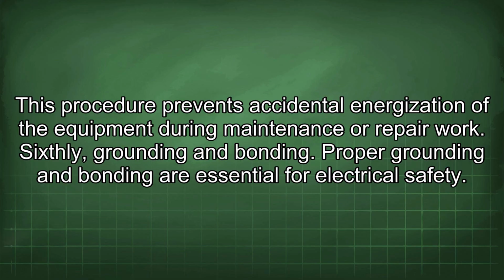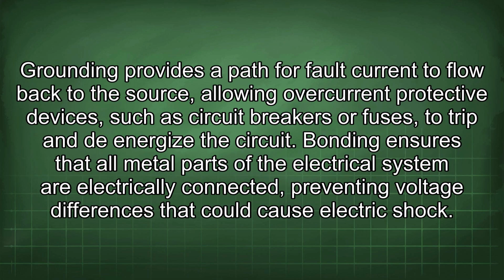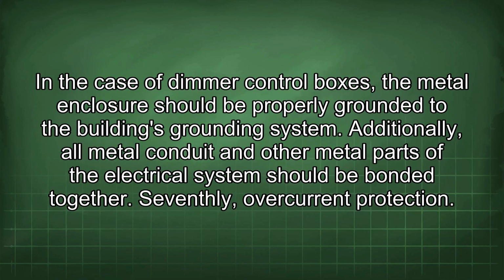Sixthly, grounding and bonding. Proper grounding and bonding are essential for electrical safety. Grounding provides a path for fault current to flow back to the source, allowing overcurrent protective devices, such as circuit breakers or fuses, to trip and de-energize the circuit. Bonding ensures that all metal parts of the electrical system are electrically connected, preventing voltage differences that could cause electric shock. In the case of dimmer control boxes, the metal enclosure should be properly grounded to the building's grounding system. Additionally, all metal conduit and other metal parts of the electrical system should be bonded together.